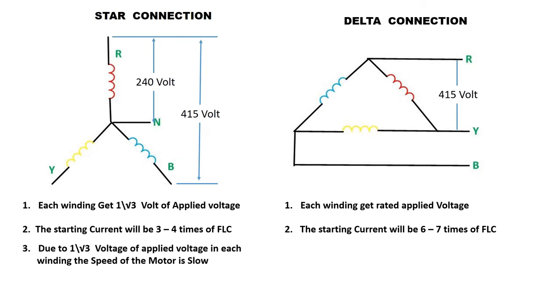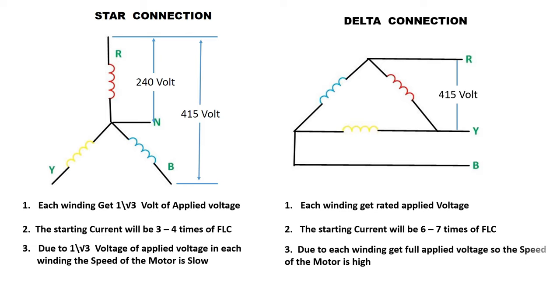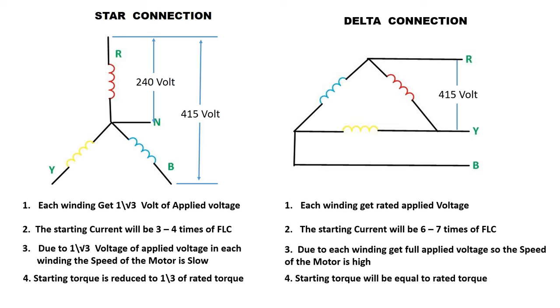The next difference is: speed of the motor running in star connection will be low, but a motor running in delta connection has higher speed compared to star connection. Besides, on connecting motor winding in star, starting torque is also reduced. But in delta connection, the complete starting torque required is provided to the motor.